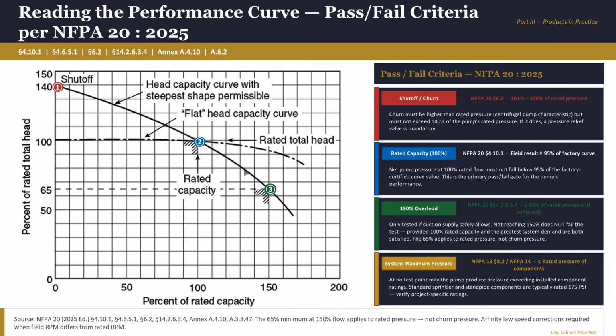If it can, the pump can handle real emergency demand. The 2 curves on the slide show different pressure and flow. You got one right here and one right here. This one, the pressure drops fast as flow increases. And the other one is constant or almost constant pressure. Holds pressure more steadily across the range. Both are allowed and permitted, but the flat one is generally better.